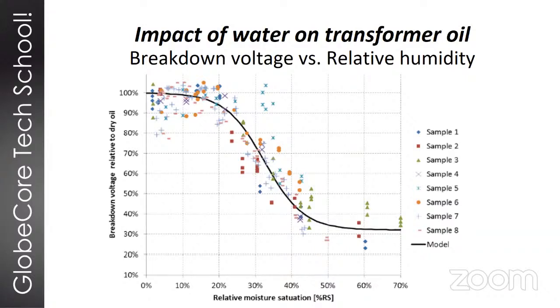And low BDV means that the insulation system cannot prevent electric arcs. And this means that electric arcs happen inside the transformer, generate a lot of gas and decomposition compounds, which will have a negative impact on the transformer and will reduce the transformer life cycle. And this graph comes from the Vaisala company. They did it by continuous monitoring of 8 different cases and then building this graph based on their online monitoring systems. Okay. Right. Next slide, please.